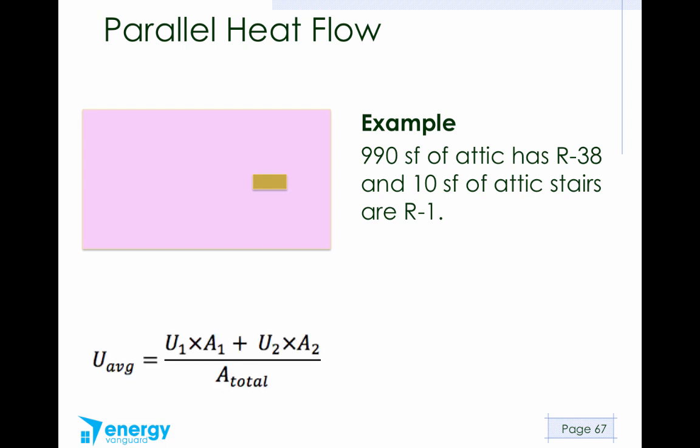We apply this formula. U average equals U1 times A1 plus U2 times A2 divided by A total. Remembering that we're given R values here, but we have to put U values in the equation. We know the relation between R and U. If we want U and we know R, U equals 1 over R. So here's what we've got. Pathway 1 is the insulated part, and U1 would be 1 over 38. A1 would be 990. So we do this first, and here's a little tip for you. Instead of doing 1 over 38 in your calculator and then multiplying that by 990, the easy way to do this is just 990 divided by 38. It gives you the same exact answer.